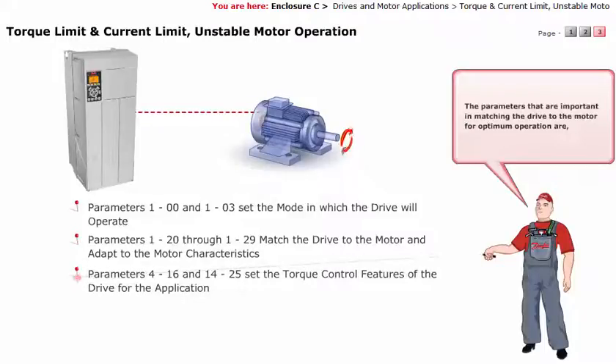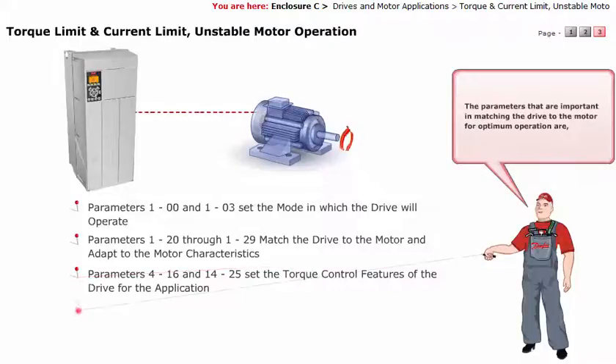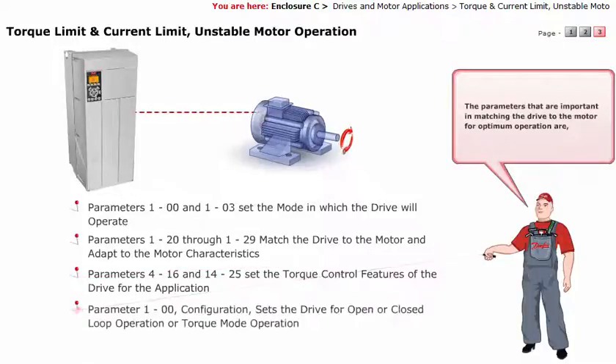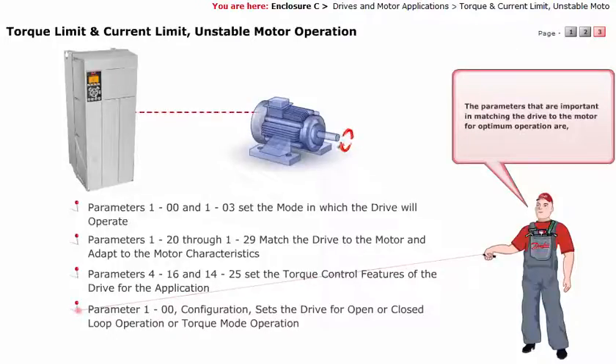Parameters 4-16 and 14-25 set the torque control features of the drive for the application. Parameter 1-00, configuration, sets the drive for open or closed loop operation, or torque mode operation.